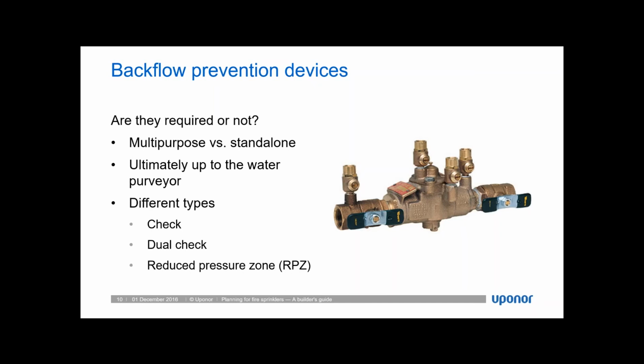A water purveyor may call out the requirement for an RPZ because that's the language that's used in some of the cross-connection booklets that are provided from various water authorities. However, if you go further into the requirements for backflow prevention, the RPZ is not always going to be required if we're talking about residential sprinkler systems. Often that term is used when a dual check valve or detector check valve should be used instead. Reduced pressure zone valves often have requirements for costly annual maintenance that should be avoided if possible, because we don't want additional costs to be incurred by our future homeowners.